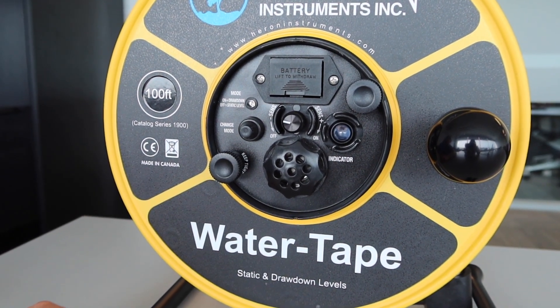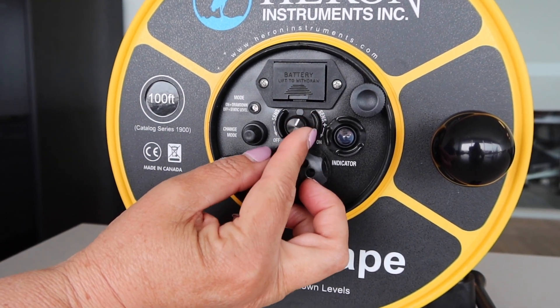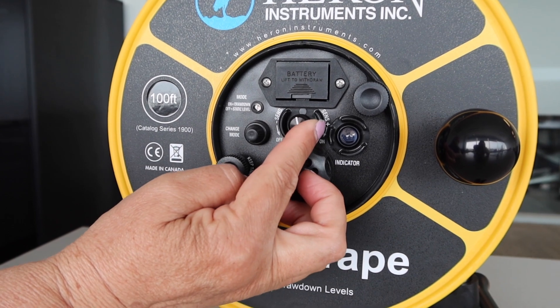If there is any cascading water in the well, simply adjust the sensitivity dial until you get a clear, crisp, consistent signal when the probe touches the water.